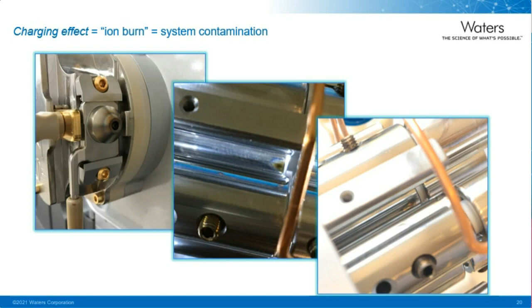System contamination can affect the data as shown in this example. This is fake data, so I made this up for example purposes. And we see a drop of peak area over time as we keep the system running complex samples 24 hours per day, every day. The bottom plot shows the area ratio, and we can see the ratio of analyte over internal standard is consistent over time. So when using labeled internal standards, the quantitation is not impacted, but over a certain period of time, the response becomes too low and is not acceptable anymore, especially for low concentrations or for less sensitive analytes.